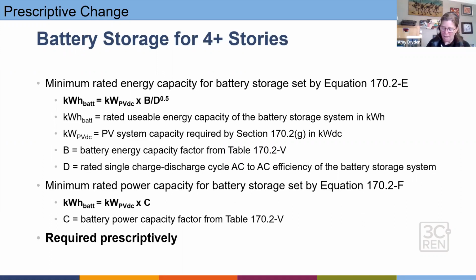Okay. And then we have battery storage. So this is battery storage for 4+ stories. We have a couple of different things. We're looking at the minimum energy capacity for the battery, and we're also looking at the minimum rated power capacity. So we have kWh, right, is my energy capacity and what I can provide. And then I have a minimum kW, which is my power. So this is required prescriptively. You have to meet both of those equations that are shown here. And you're going to be looking at kind of the specification sheet. You'll be doing this approach and then looking at the specification sheet for your battery to see if it's going to meet these requirements. There are some exceptions for providing battery storage for 4 stories or more.